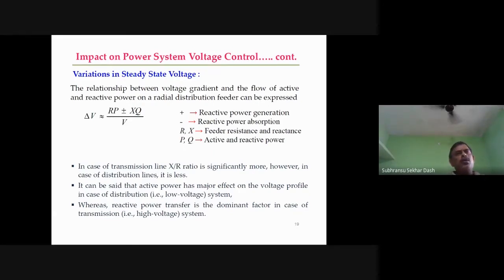Impact on power system voltage control. Variation in the steady state voltage. The relationship between voltage gradient and the flow of active and reactive powers on a radial distribution feeder can be expressed in terms of (RP plus XQ) by V, where reactive power generation is positive and reactive power absorption is negative. R and X are the feeder resistance and reactance. P and Q are the active and reactive power. Plus or minus depends upon leading and lagging. In case of a transmission line, X by R is significantly more. However, in case of a distribution line, it is less.